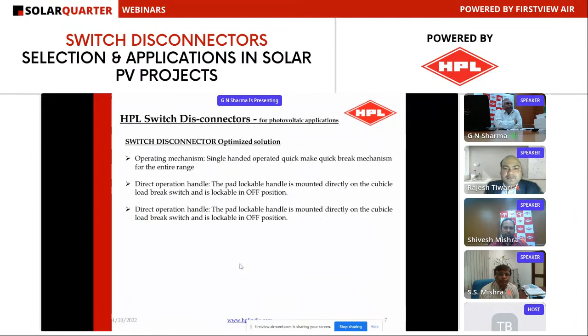We also saw that during installation, sometimes the mounting position of the switches becomes an issue, so we designed multiple mounting options with multiple positions that can be fitted. We also gave factory-fitted auxiliary contacts with a potential-free control circuit, since in DC it is very difficult to get accessories. Then castle lock provision is also there for further mechanical safety, and door interlock facilities are available. If somebody wants to build a panel with openable doors, since it's DC and voltage levels are very high, people require a lot of safety measures, which we have provided before opening the door.